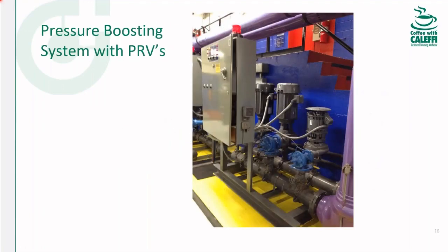So here's another, what I would call old school system. This is a booster with single stage close coupled end suction pumps. And we've got PRVs on each pump again. But if you notice, one of the pumps is smaller than the others. There's a lot of terms for that, but I've always called it a jockey pump or low flow pump. And the intent here is that the jockey pump takes over during periods of low demand, and then the larger pumps take over to handle the higher peak demands. So with VFDs coming into play, these are pretty much obsolete.